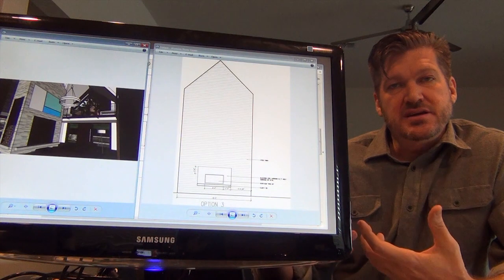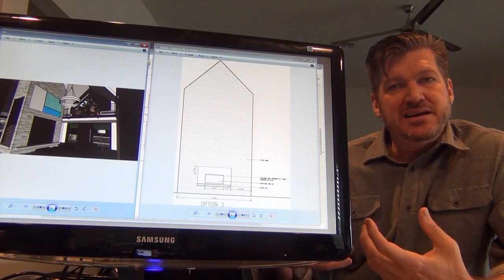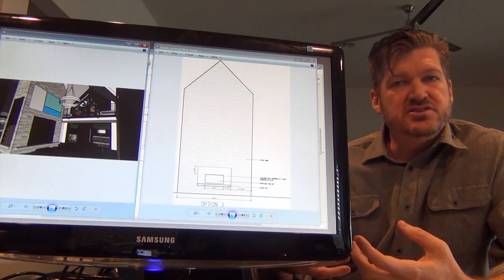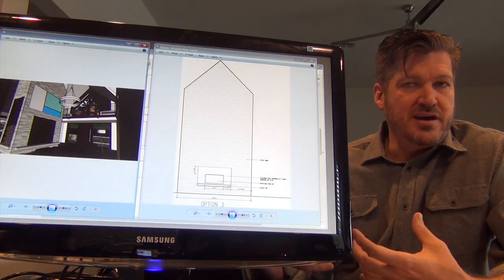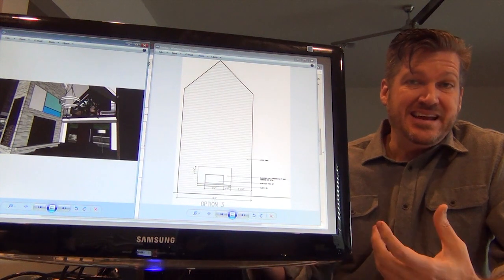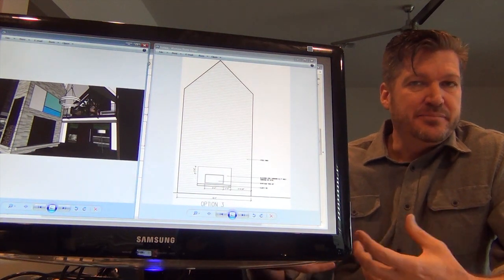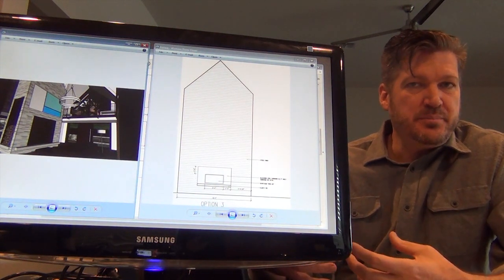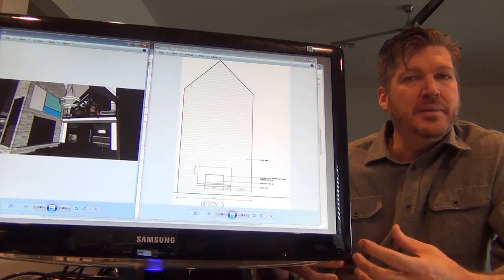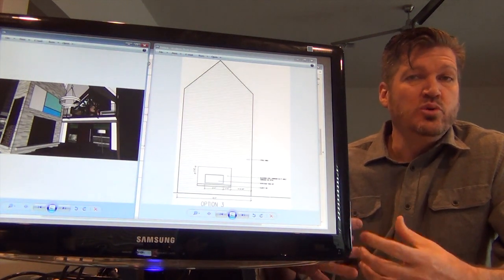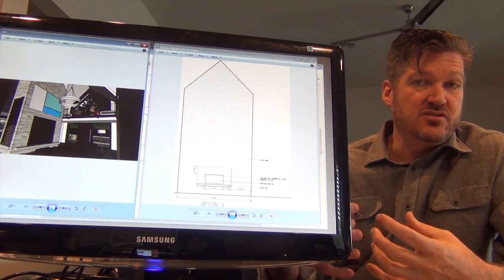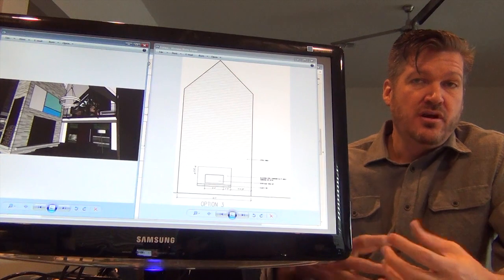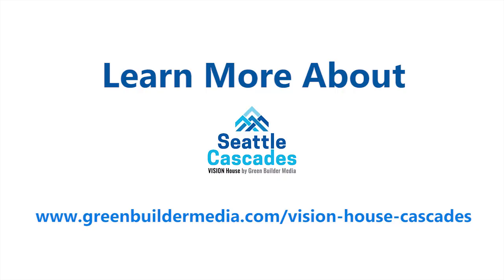What's really interesting is we're looking at designing the ventilation system to charge that thermal mass at night in the summertime to depress that temperature and to be one of the key thermal masses that hold a cool temperature in that house during the summer throughout the day with no air conditioning.